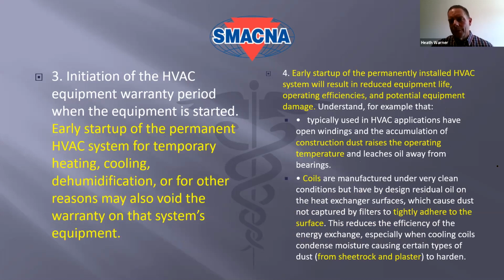Early startup results in reduced equipment life. Another one that most people don't want to talk about, but construction dust not only raises the operating temperature within the equipment, that raised operating temperature significantly reduces its life, depending on how much gets in there, because every construction site is dirty, no matter how much filtration you have. The one I really didn't think about was the coils. All coil sets are actually manufactured in clean rooms. They're designed to be totally isolated and sealed away from all contaminants. Sheetrock, plaster, sorry Thad, drywall dust is a big, huge problem for coil sets. We're actually doing a disservice by using the permanent system during the drywall phase altogether.